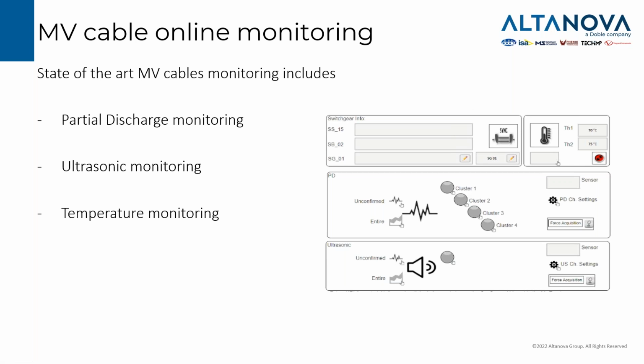So for medium voltage cables, we can monitor three main things: partial discharge, ultrasonic signals, and temperature at the termination. Normally, it's hard to have something that is distributed along the medium voltage cable line. So we have as an access point for detection the terminations only, and we can have a better survey by analyzing these three parameters. Here is the user interface of our monitoring solution for medium voltage cable termination monitoring. There is temperature, PD, and ultrasonic signals. We can have a dedicated alarm for each of them.